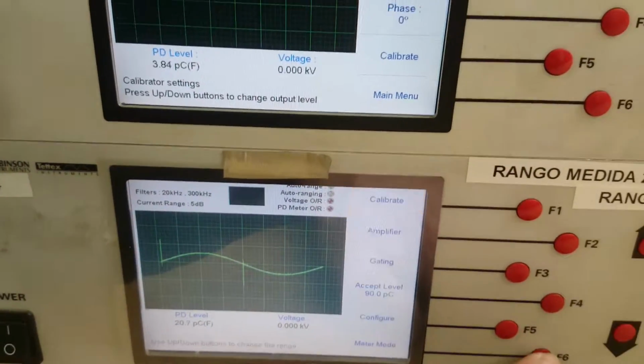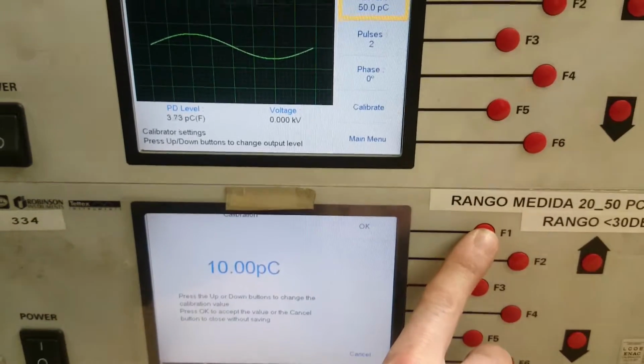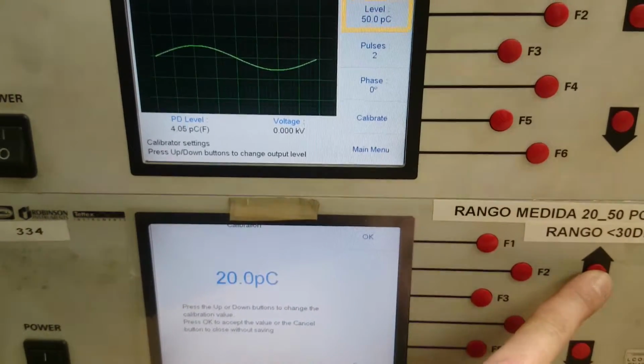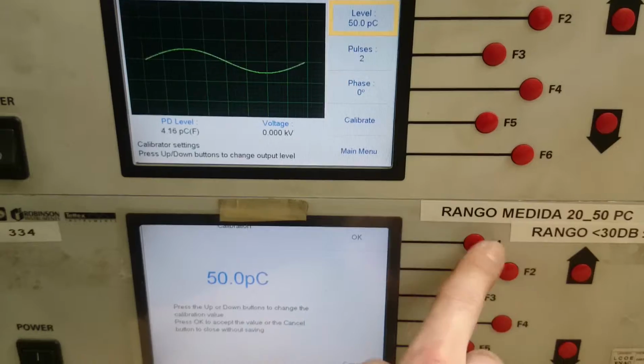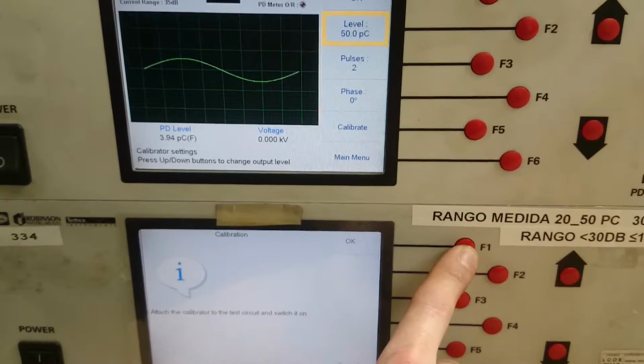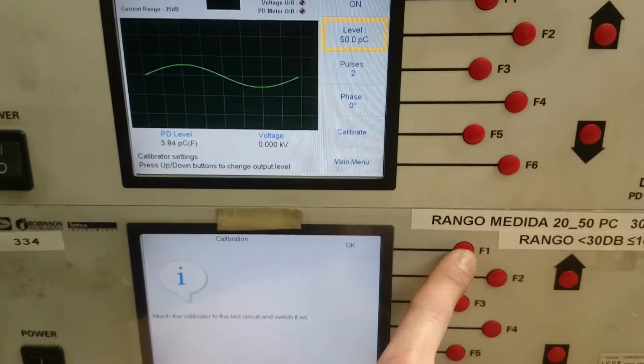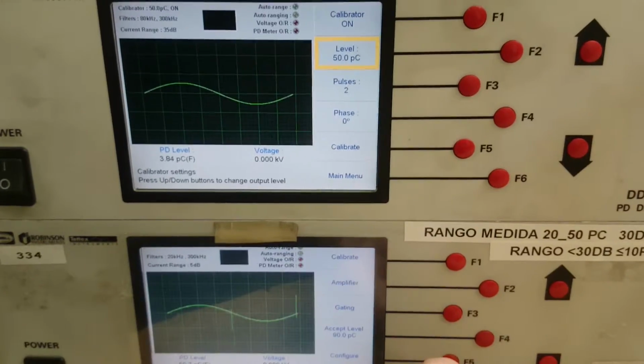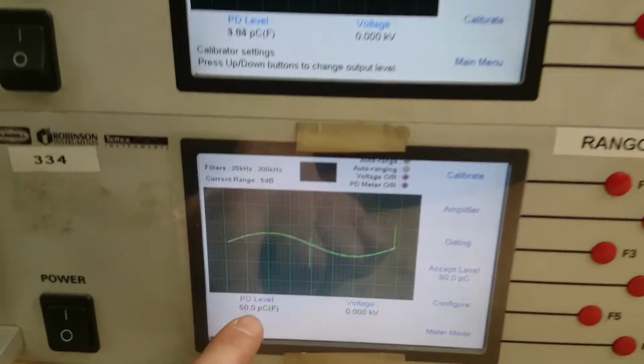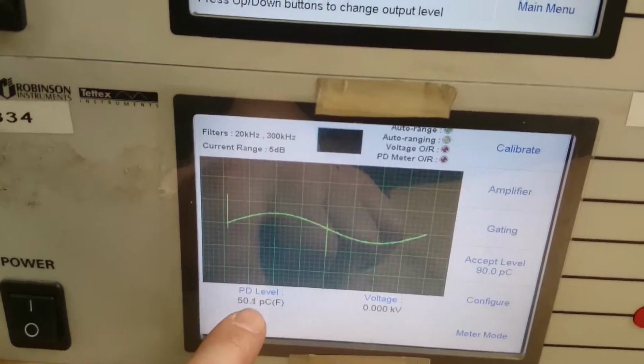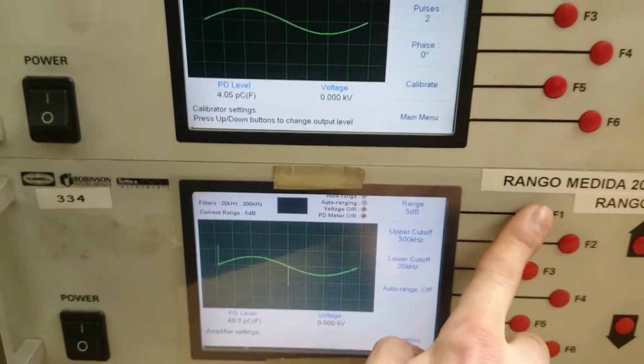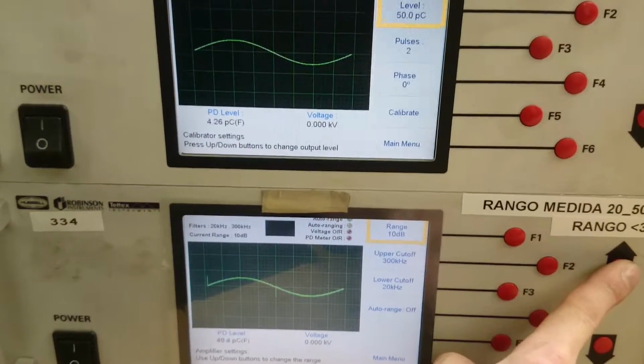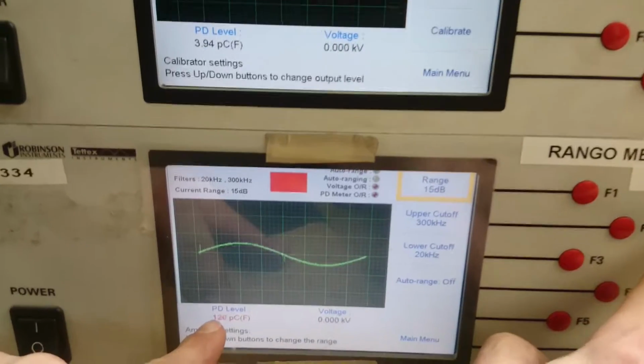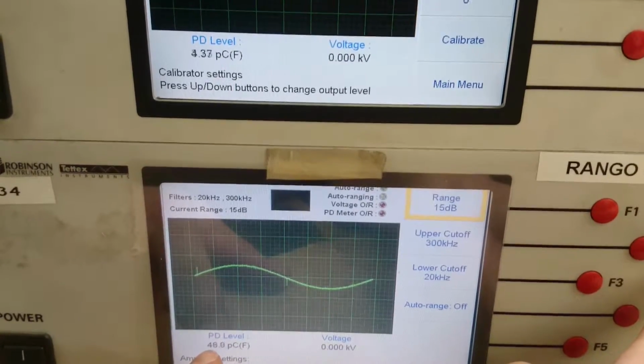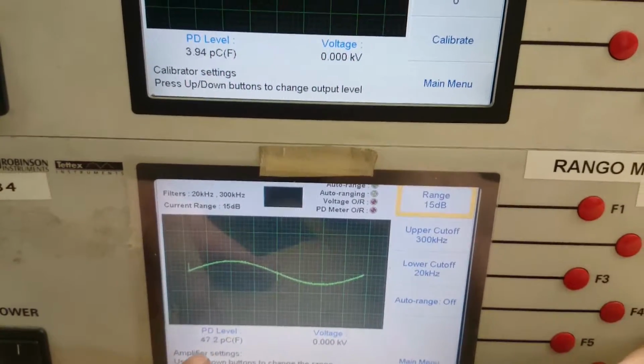So main menu, calibrate, manual calibration, set that to 50. Okay. Attach the calibrator to the test circuit and switch it on. Okay. And now it's set to 50. So that's calibrating correctly. I'll just change range. 10 dB. Still reads 50. 15 dB. Still reads 50. So that's good.